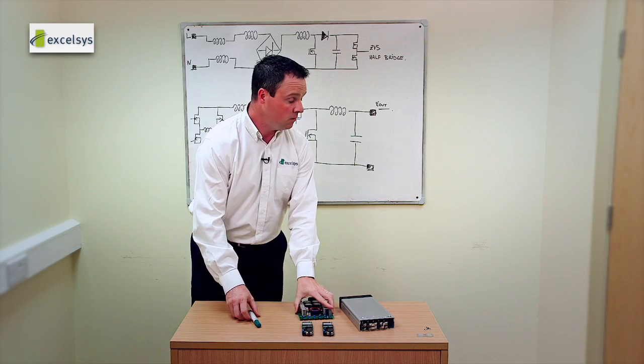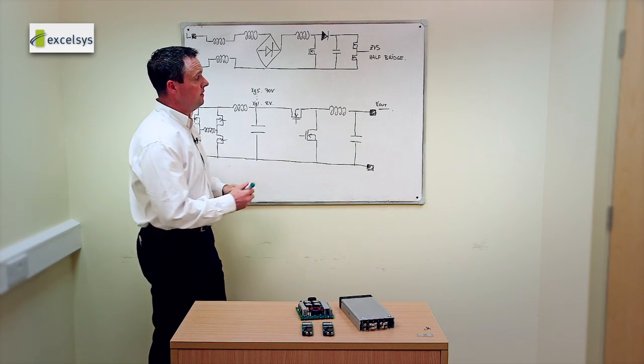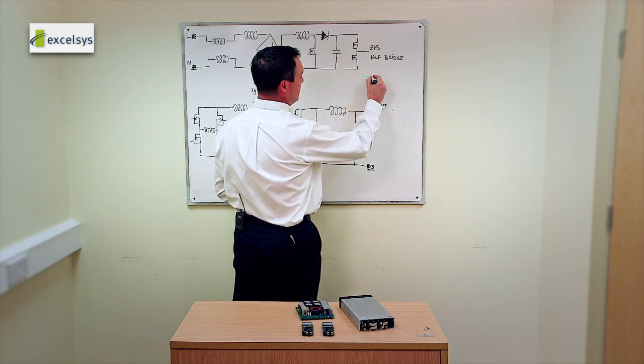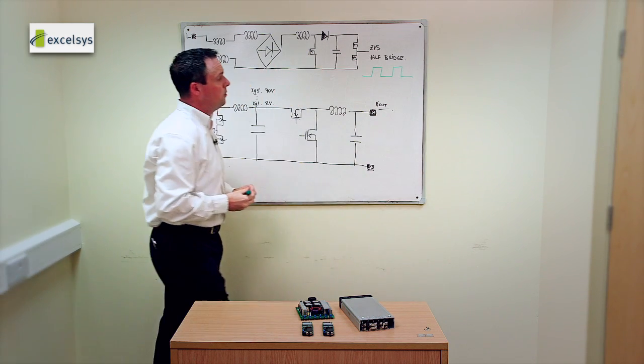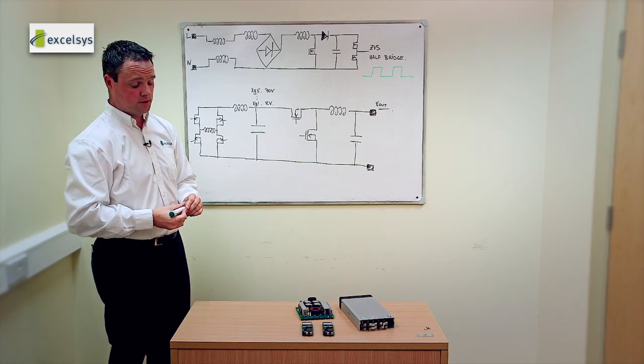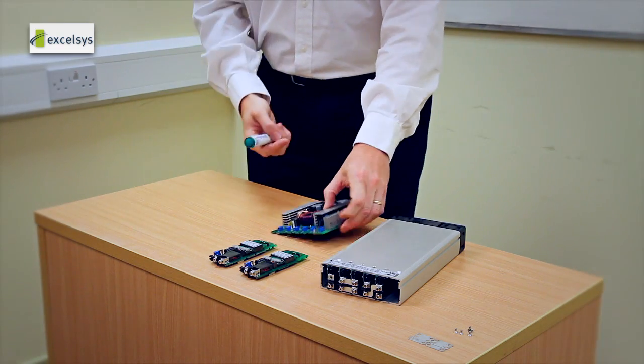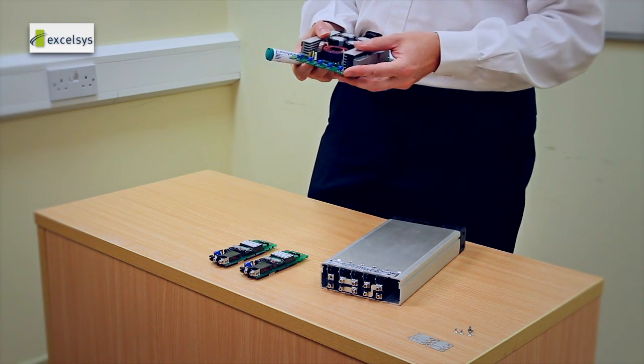We then take a bridge rectifier and we rectify the mains and we boost the voltage to approximately 380 volts. From then, we have a ZVS half-bridge in which we generate a fixed duty cycle of 50%, plus and minus 185 volts. And this is what we use to power each of the individual power mods.